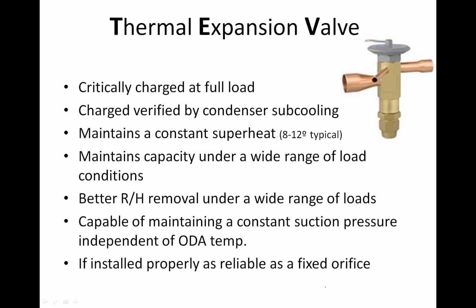Right, so sometimes you're talking about excessive length, line, and lift. You may have to increase your subcooling from maybe 10 degrees to 12 or 13 degrees of subcooling to compensate for that drop in pressure. And really the correct way of doing it is to increase the liquid line size so that we decrease that pressure drop. That's where it's said, if you're going to a longer line set, consult the manufacturer to see how they want you to correct that problem. Maybe a slight increase in subcooling. Maybe you have to change the liquid line to make it operate correctly.